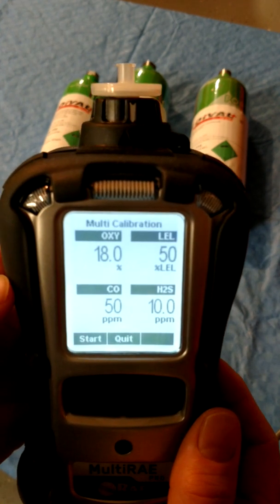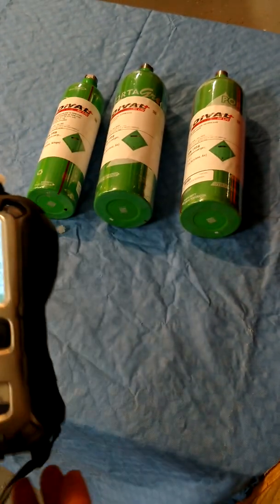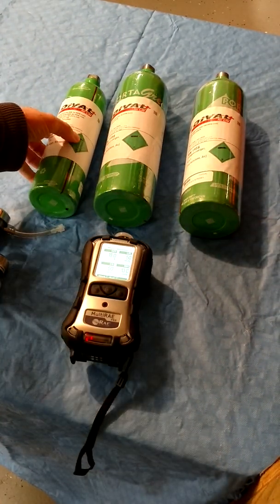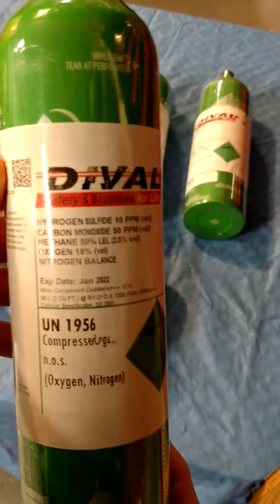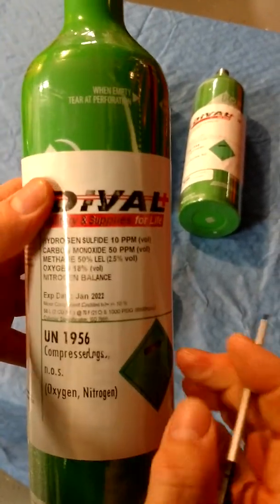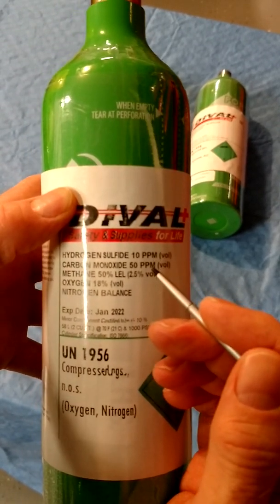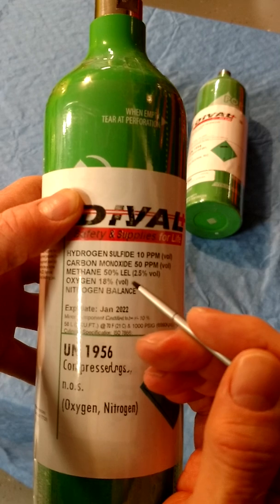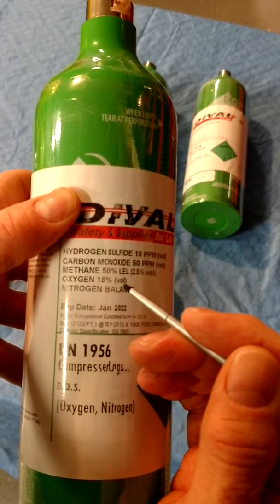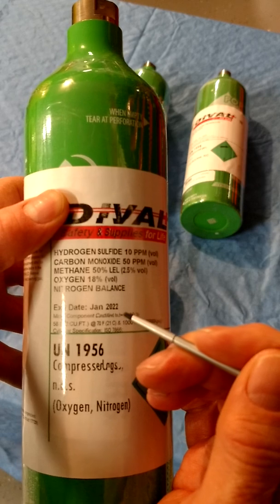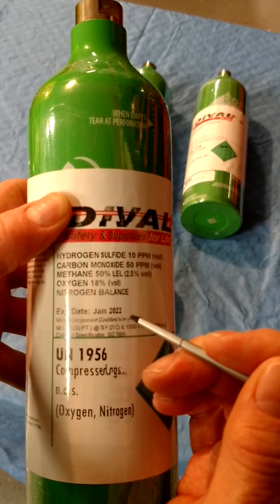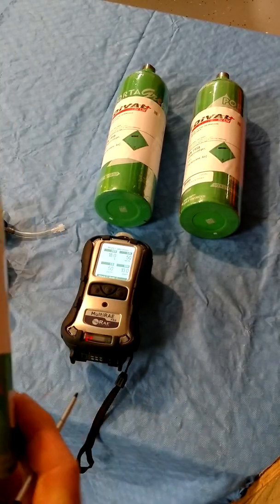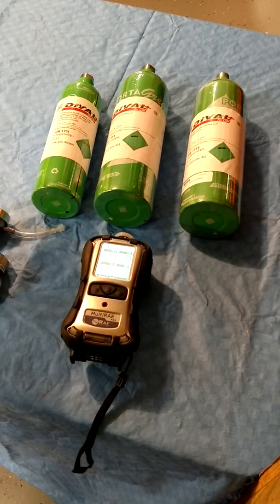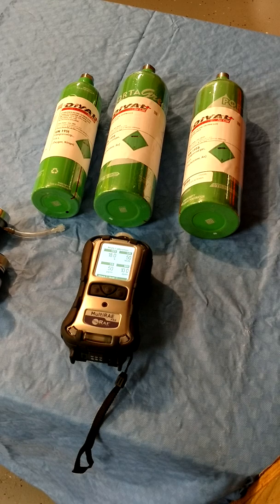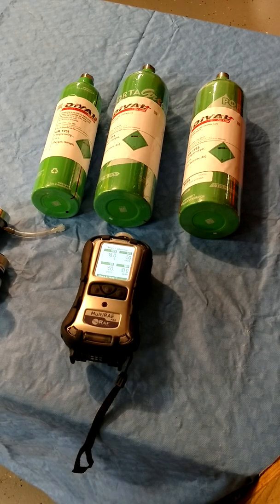Now we're going to check our gas bottle to ensure that they are the same. And you can see hydrogen sulfide 10 ppm, carbon monoxide 50 ppm, 50% of the LEL, oxygen at 18%. Also, you want to check that you are within your cal due date for your cal gas, and we are. Attach your regulator to the cal gas bottle.